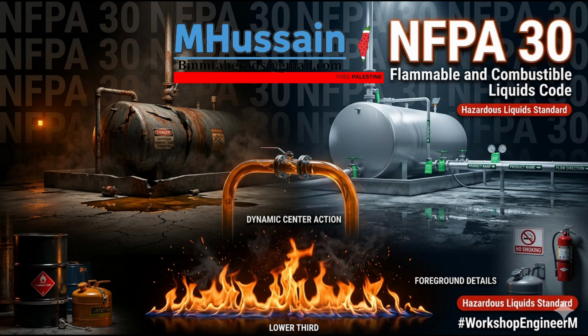If you insist on using sealed steel drums, your maximum allowable storage heights are drastically restricted, and your required water density is pushed to the absolute limits of your pumps. The code essentially forces the engineer to respect the physics of pressure.